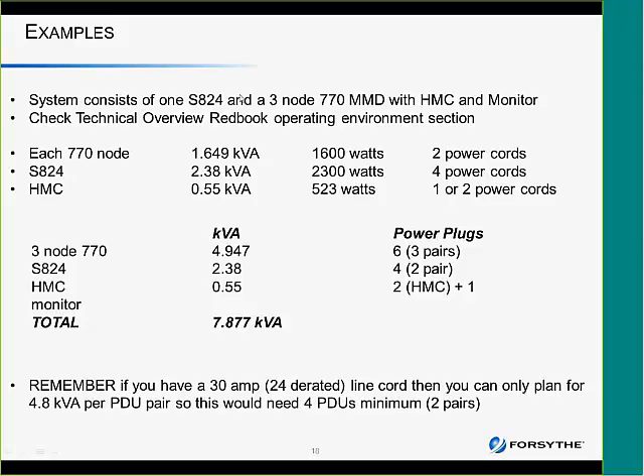Again, I've got a bunch of examples here. So here I have an S824 and a 3-node 770 MMD and an HMC and monitor. So each 770 node requires 1.649 kVA, and I have 3 of them, so it's 4.947. The S824 is 2.38, and the HMC is 0.55. The monitor is minimal, so I include that in the HMC. Each one has redundant power plugs. Basically, it comes up to close to 7.9 kVA. So on a 30 amp, I only have 4.8 kVA per PDU pair. So I would need 4 PDUs for this. And I would have to split the things across the 4 PDUs to make sure that I didn't overcommit any PDU.